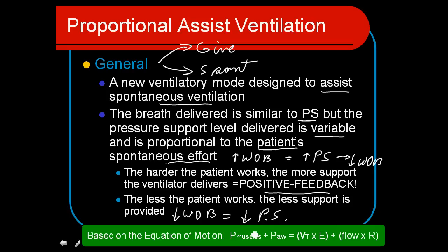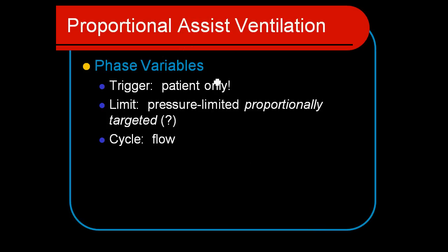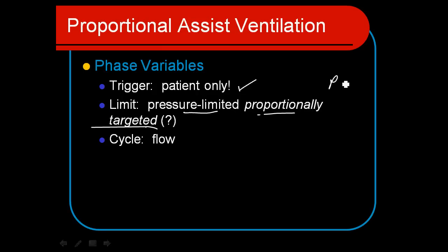Based on the equation of motion, increased work by the muscles is going to give you more inspiratory support. The ventilator picks up the patient's inspiratory effort — it's pressure limited but proportionally targeted, meaning the pressure limit varies depending on the patient's workload. It has a few ways of measuring that, and something called the P0.1 is one of them, where it measures the amount of inspiratory force generated by the patient. It is flow-cycled, just like pressure support, because in fact it is pressure support with an intelligent computer overriding system built into it.